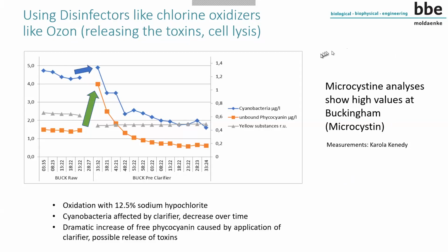Okay, understood. There was another question also: what is the minimum time interval that we can measure with our units? The algae online analyzer can measure, I would say, every 5 seconds would be a good option, but you get a large amount of values. We can also measure, I think, 1 second is possible, but less is not possible. I think that makes no sense.